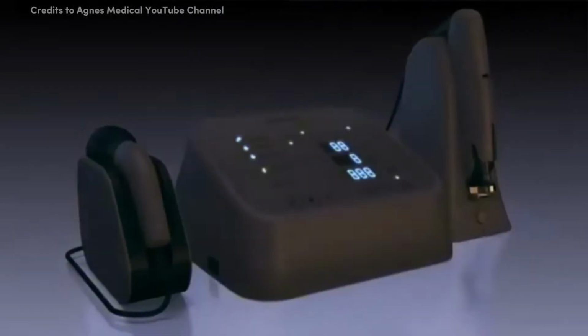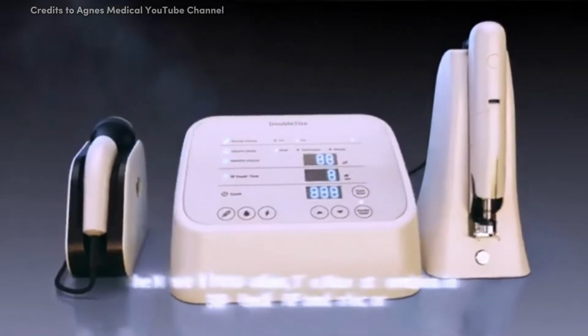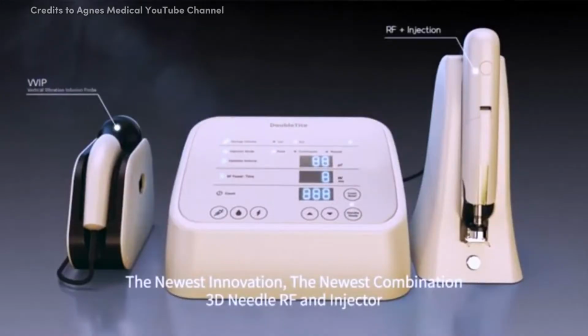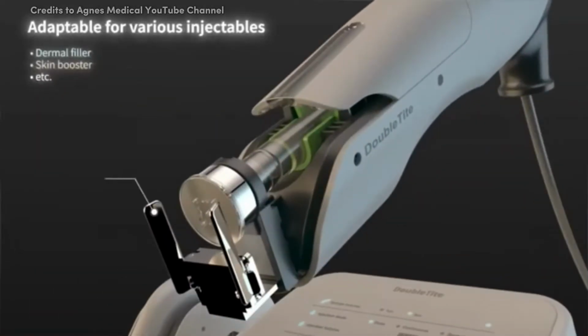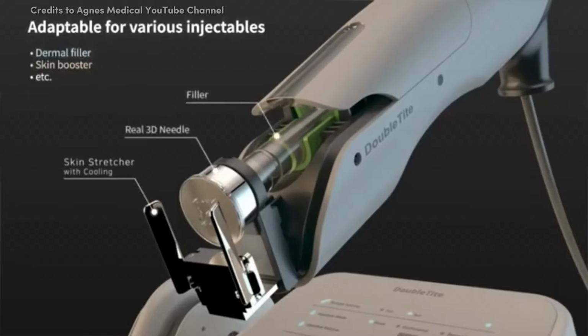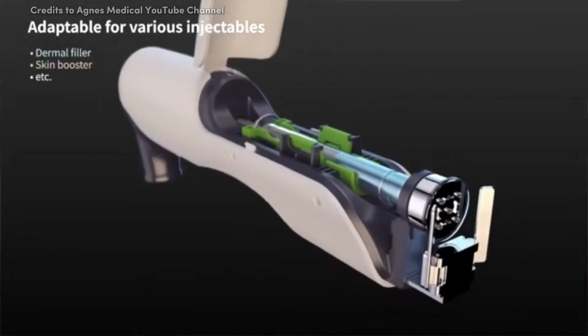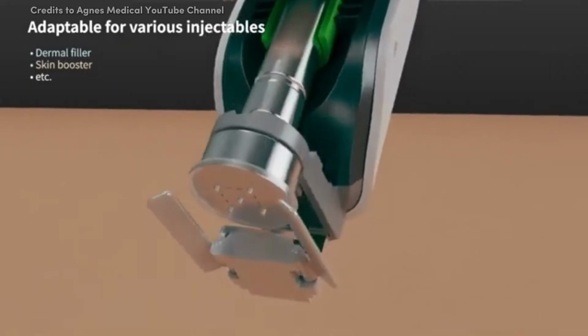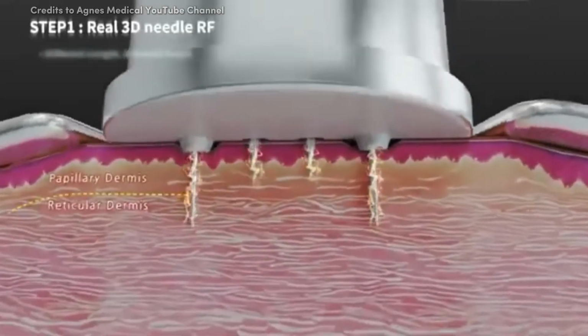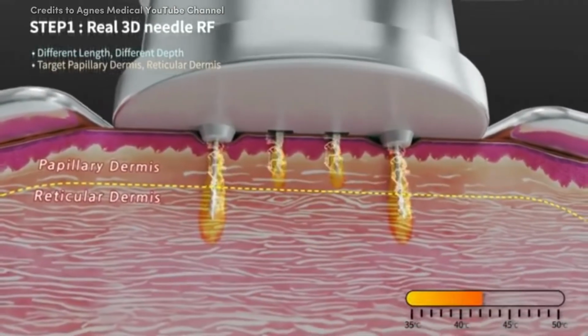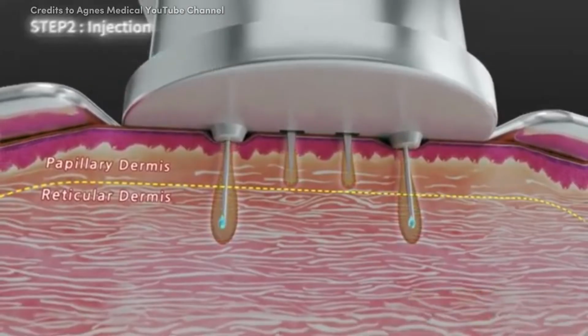Specifically, it's able to do RF microneedling and deliver a liquid or a skin booster, and actually use vibration technology to disperse the liquid. As you know, RF microneedling is a very well-known technology. You have tiny needles, and while the needles are in your skin, we can blast it with RF radio frequency energy, which sort of heats up the skin and helps to tighten up the overlying skin, as well as the underlying soft tissue to a certain extent.